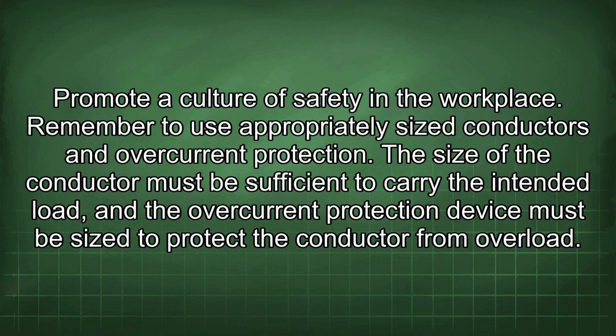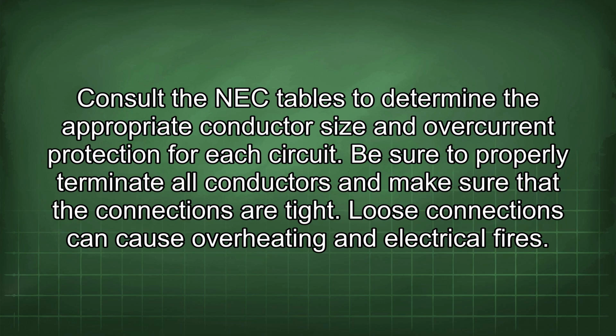Remember to use appropriately sized conductors and overcurrent protection. The size of the conductor must be sufficient to carry the intended load, and the overcurrent protection device must be sized to protect the conductor from overload. Consult the NEC tables to determine the appropriate conductor size and overcurrent protection for each circuit.